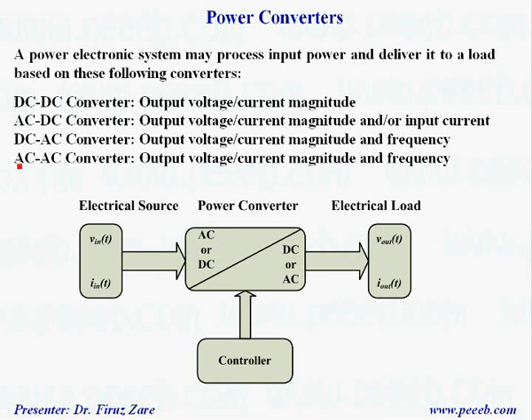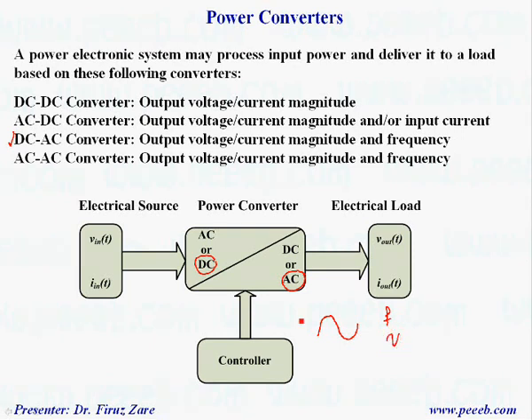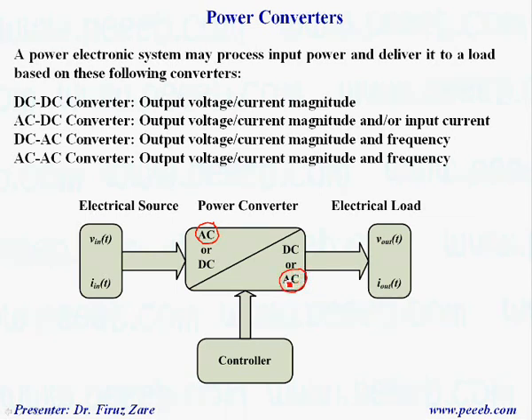The next type is a DC-AC converter, which is basically an inverter. If we have DC voltage coming from a battery or rectifier, we can convert it to AC, controlling output frequency and magnitude. The DC voltage can come from a battery or from a rectifier described previously. This type of converter is not very common by itself in industry, but can be used for special AC drive systems, and in very high power applications we can use cyclo-converters or matrix converters.